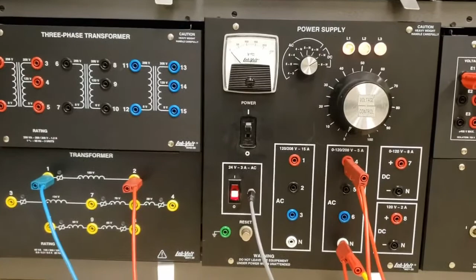But that is not the case. If you apply a different voltage than you did the test at, you're going to find your RC and XM values are actually different, which is terrible - that's not good at all. These values should be constant, or at least that's what this test is trying to tell you. The book and in class make you think these values are constant regardless of voltage, but it's not.